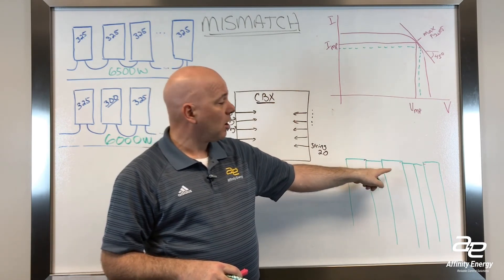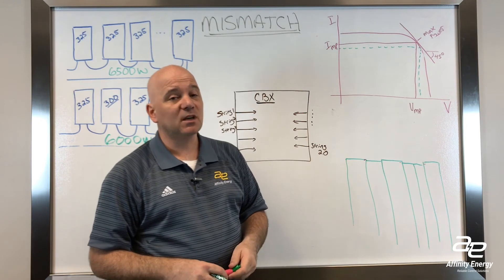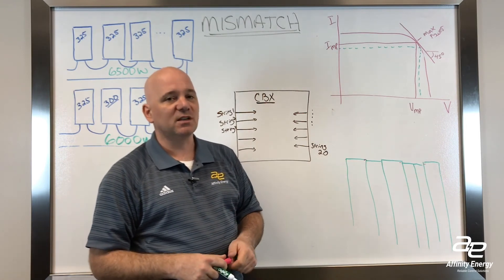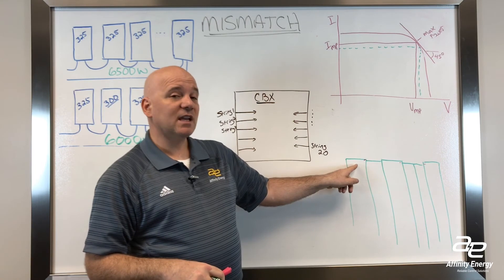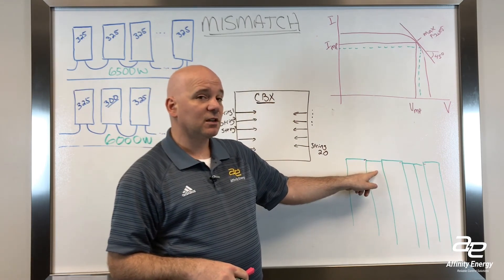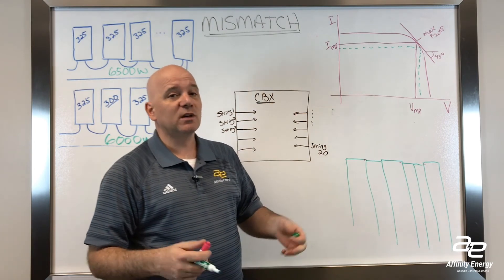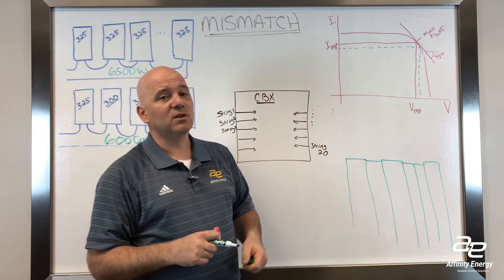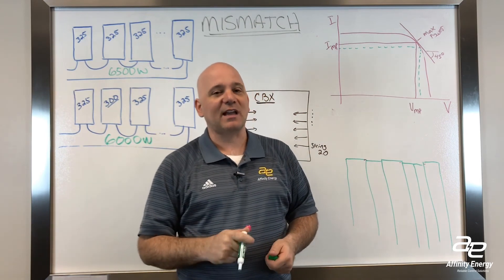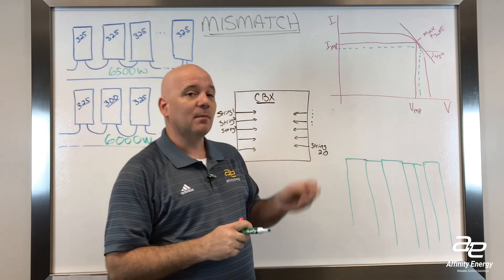Those things are hard to troubleshoot and detect with a normal SCADA system, because you're really looking at 195 to 200 amps at a time. Normalizing the data in order to find those very small differences is critically important — this is really the only way you could see it at a macro level, unless you went out and put individual instruments on each of the individual strings to try to quantify exactly what their current contribution was back to the combiner box.